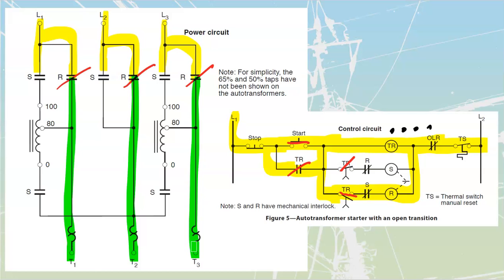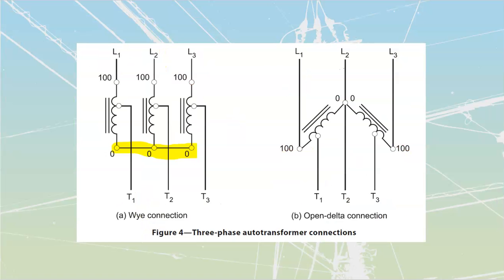It's an open transition type of autotransformer. What type of autotransformer is this? Well, this has two windings across it, and we see that we've got the two windings connected directly up to one of the lines. There's no star point because it's connected onto that line. What we're looking at is an open delta autotransformer.